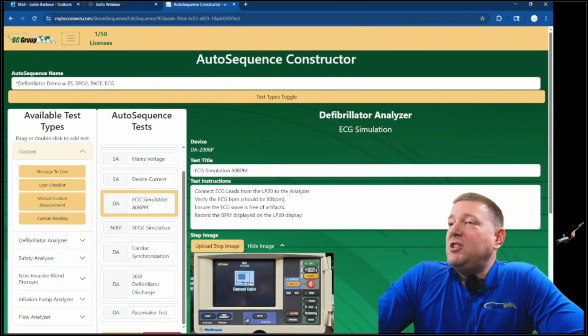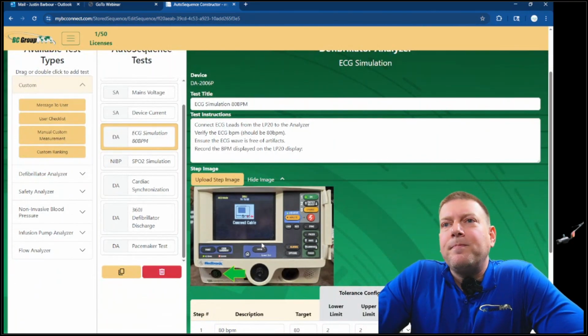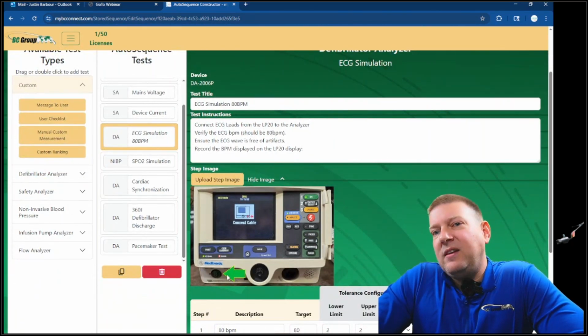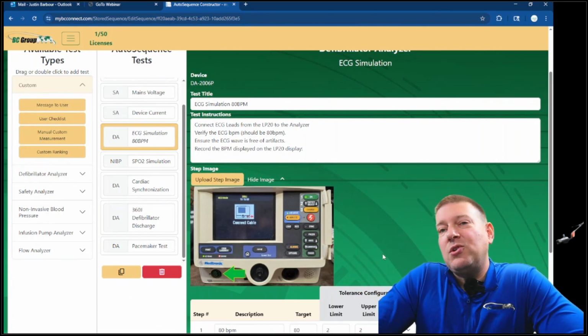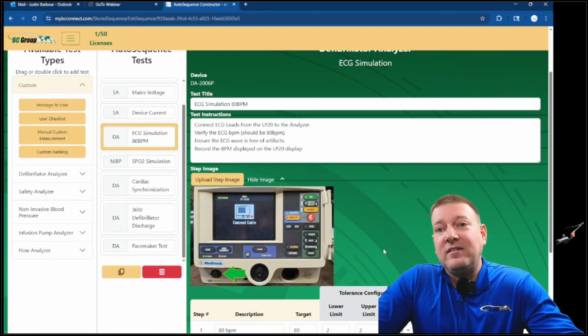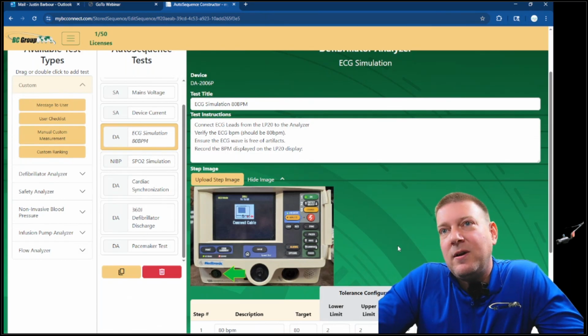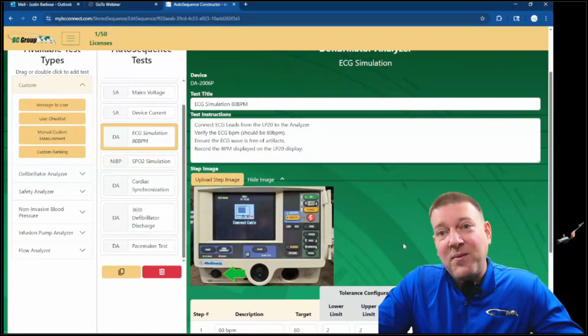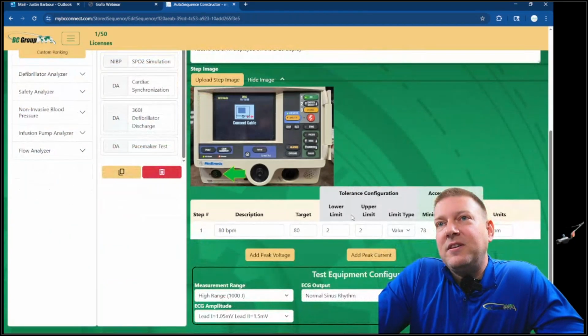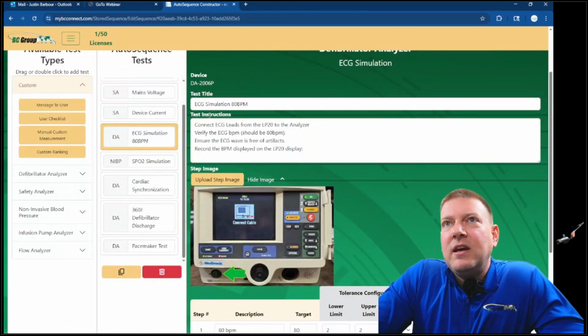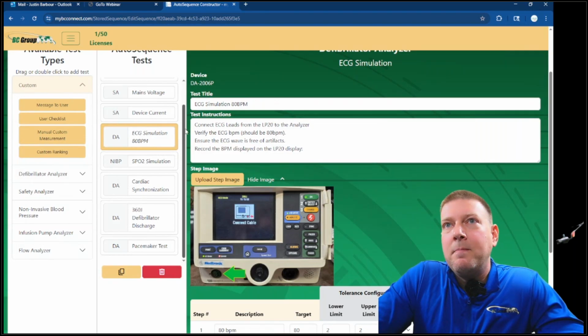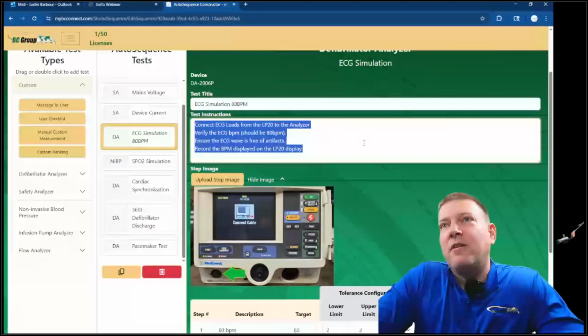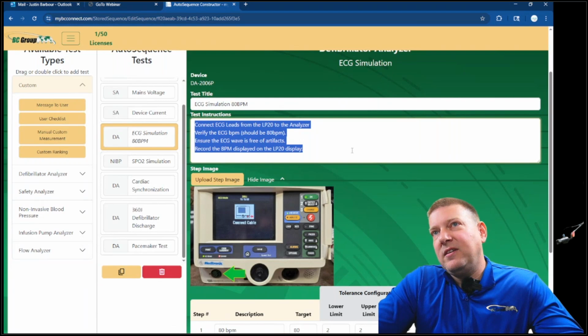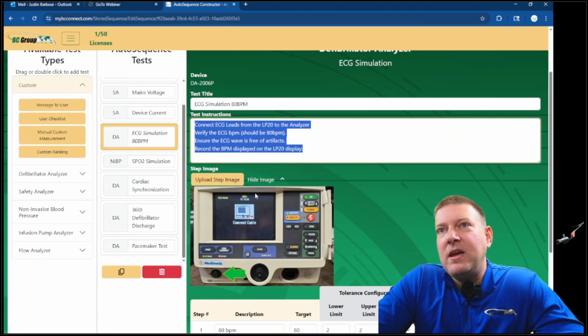So right here, ECG simulation. It's another step. I show with Microsoft Paint exactly where I want the cable plugged in. And I should have another image showing how the ECG cables are connected to the top of the defibrillator analyzer. That way they know exactly how I want it set up. But this is just one step. You can see I label it as 80 BPM, and I give them instructions of what I want them to do. So connect it to the analyzer, verify the BPM on the display, and record it.